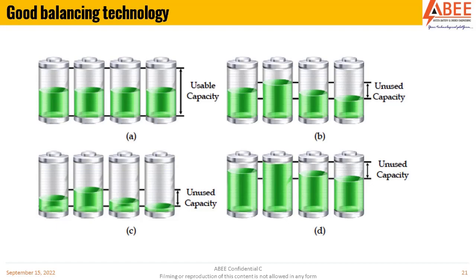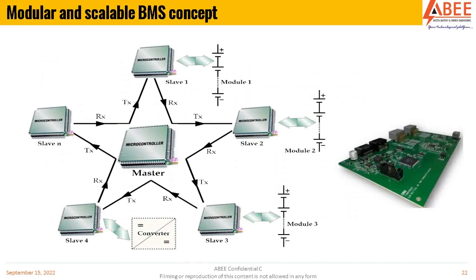Many problems that have occurred so far, explosions with home storage batteries, were actually related to cell balancing failures, or the cell balancing current not being sufficient. In that regard, BMS is very important - a BMS which is cost efficient, modular, and scalable, both in series and in parallel. That's what we call a master-slave combination, which can be easily adapted to different scenarios, for low voltage, high voltage, or parallelized solutions.